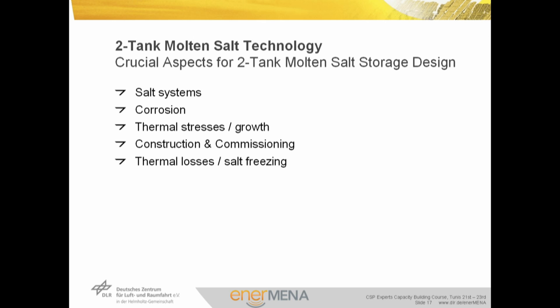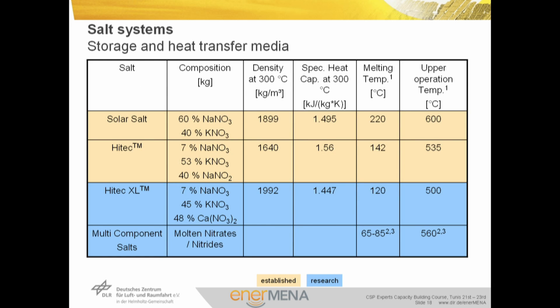Detailed knowledge about the corrosion process is important for cost-effective design, as is knowledge about heat transfer mechanisms to the environment. The cost for insulation should be compared against efficiency losses. Special care must be paid to the initial filling procedure — molten salt must always be kept above 250°C. Today's most popular molten salt is a mixture of potassium nitrate and sodium nitrate, operable between 220°C and 600°C. Another commercially available option is Hitec salt with a lower melting point of about 142°C but also a lower maximum temperature and higher cost.